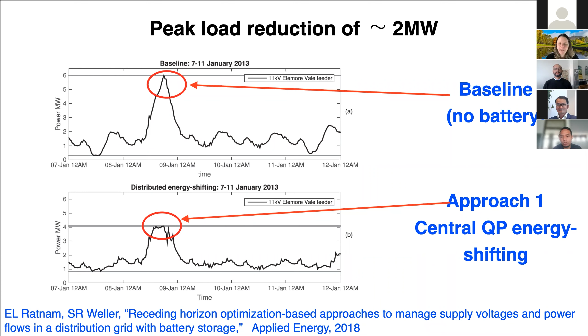So the top figure shows the case when batteries are not scheduled, with peak load along the distribution circuit at 6 megawatts. In the bottom figure, we implement the receding horizon QP energy shifting approach, reducing the peak load from 6 megawatts to 4 megawatts, deferring capital expenditure. But what about the supply voltages?